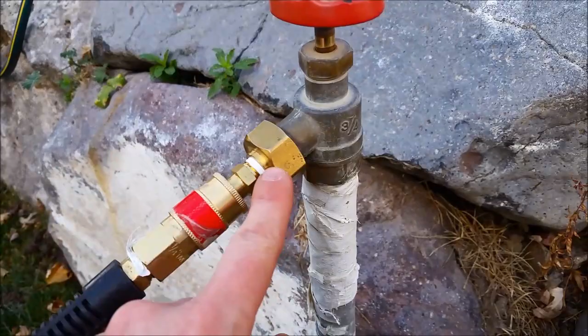Right now the main water shutoff is turned off, so even if I turned this on and unplugged it, there'd be no water coming out. What I do is use this air hose and adapter to pressurize the sprinkler system with air pressure instead of water pressure, then turn on each individual station to flush out any excess water left in the lines, making sure nothing's left in the pipes to freeze over the winter.